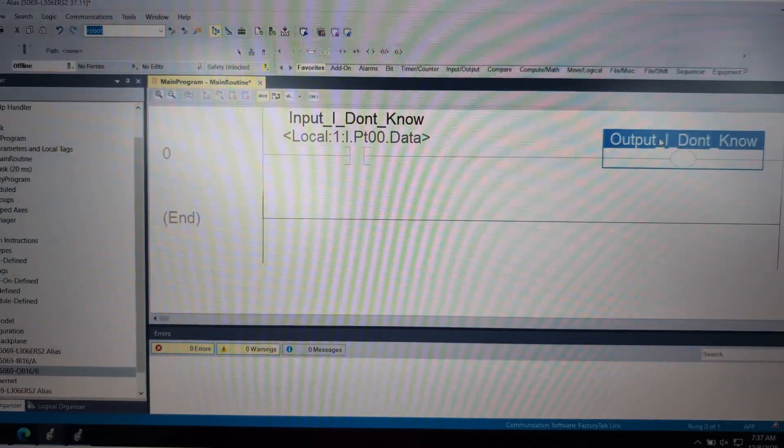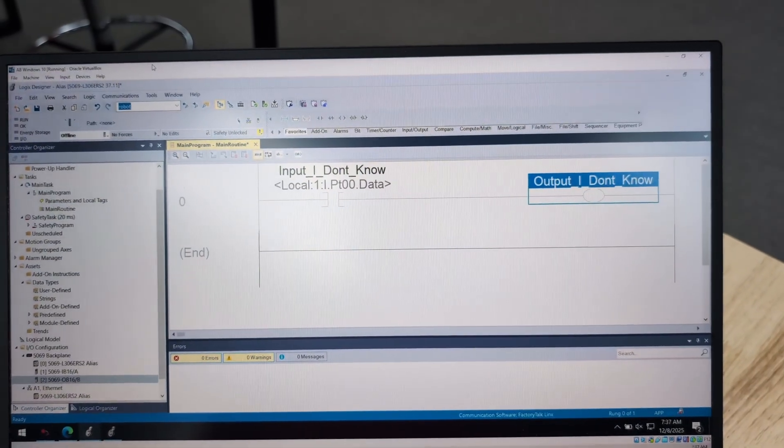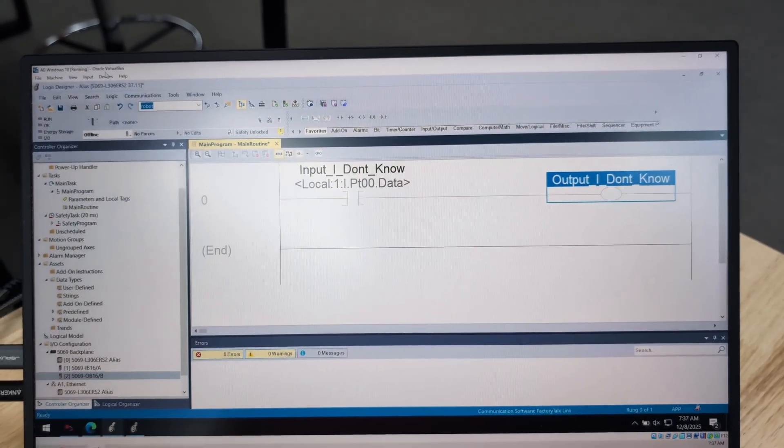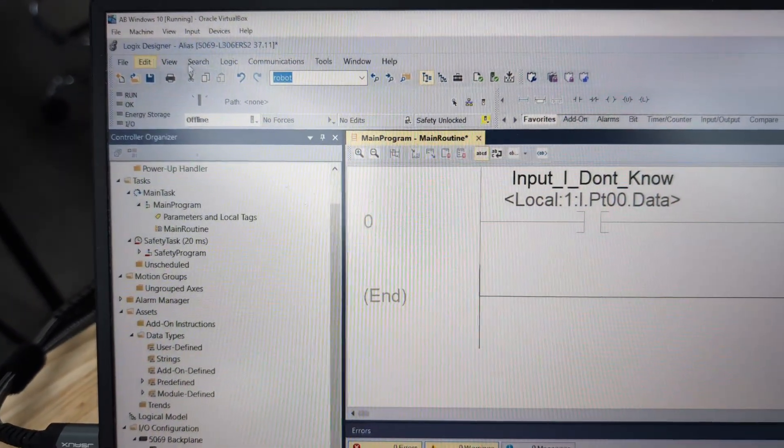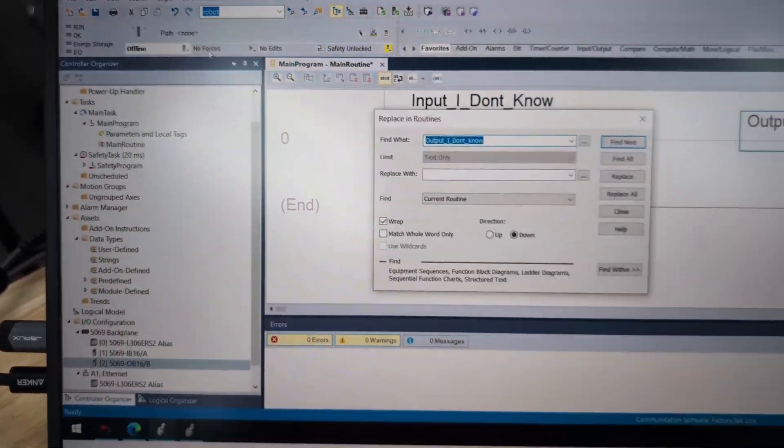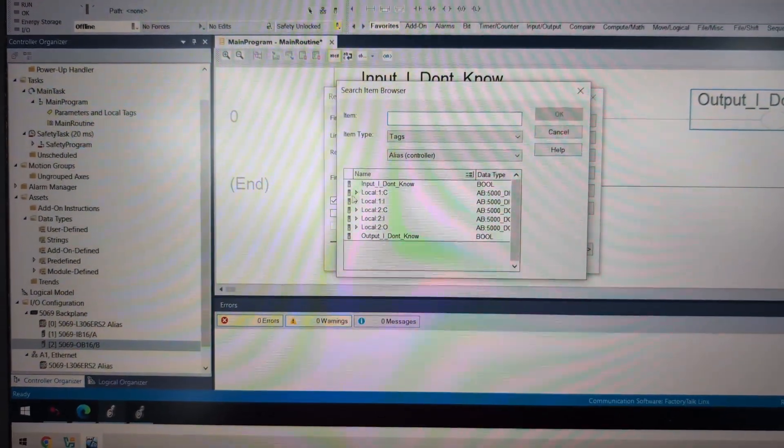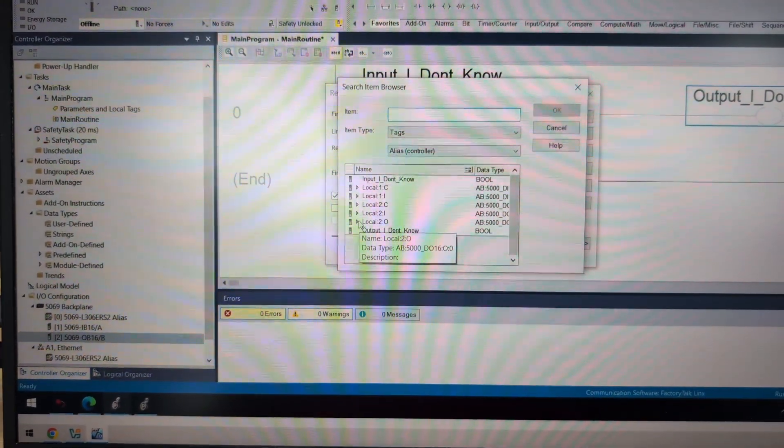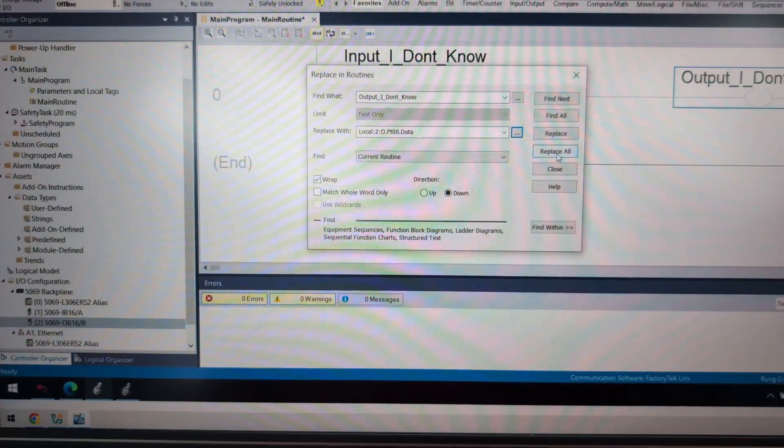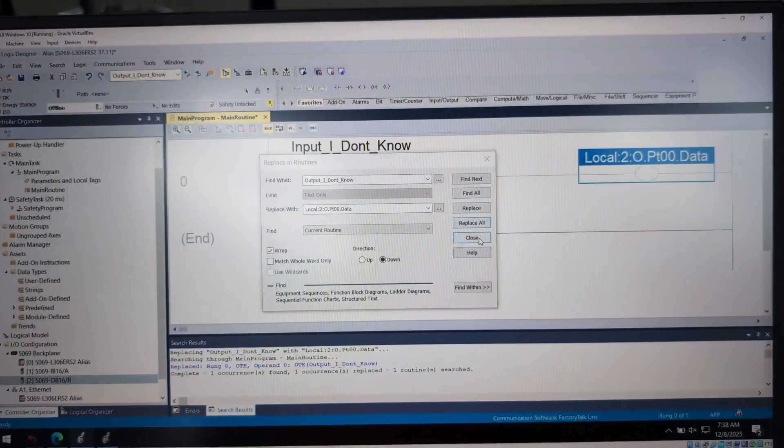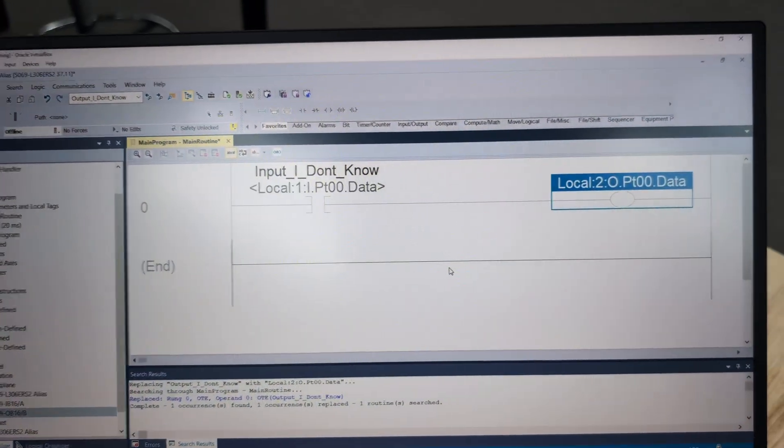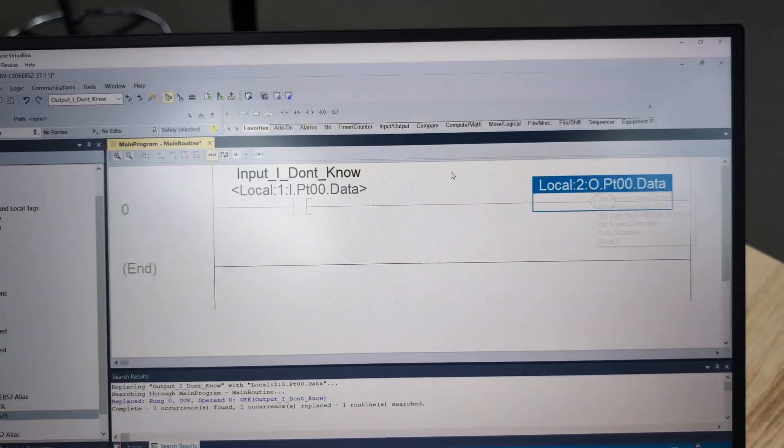Now my counter to using alias in this situation is long term, us knowing that that's local:1:I PT00.data is more important than that convenience you had in that little bit of time of development. So why don't we just use the replace function. So instead of doing that, we could highlight I_dont_know or output_I_dont_know. And we could go up here to search, replace. And that will replace all instances of it throughout the program.